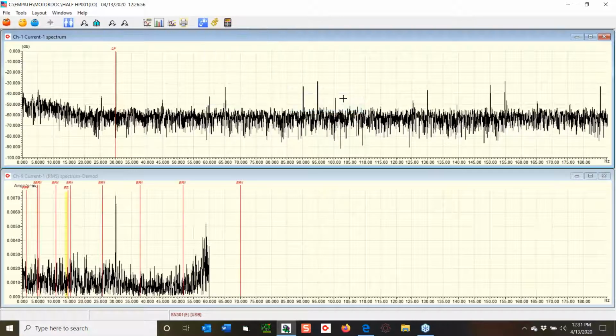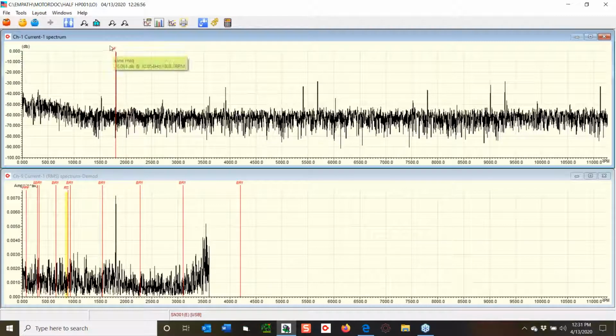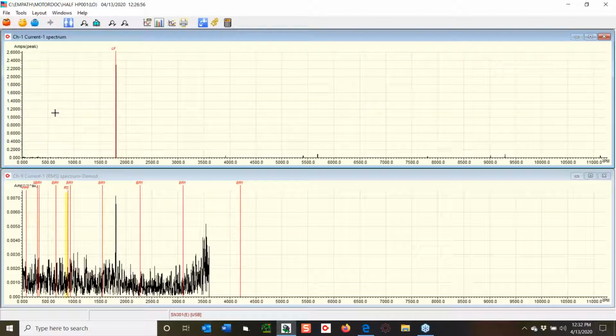The other thing I can do is come in here, and if I think I have bearing damage, I can highlight this. It'll identify where the peaks are in my linear scale down here, DMOD. I can also start working with my different types of filters, and I can even change the minimum dB level. If I think the noise floor drops below here, I might set it down, say to -120. I can change frequency to RPM, especially if you happen to be a vibration analyst and you're used to working with that. I can also switch it over to linear so it shows in true current each of those frequencies.